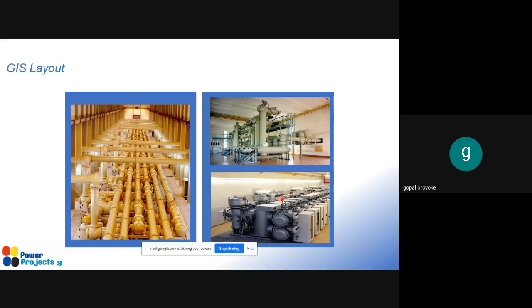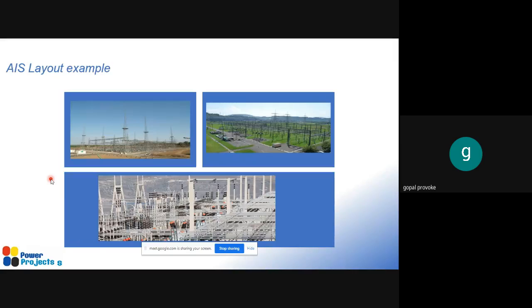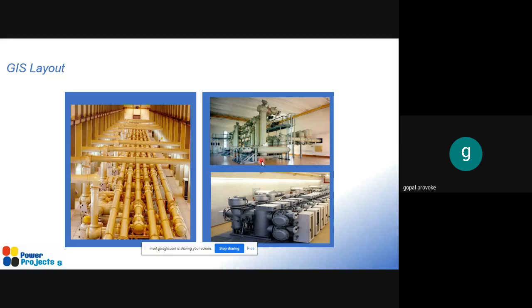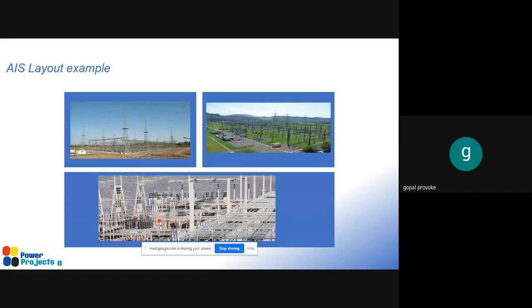And if you have visited metro stations, there is a gas insulated substation near Alandur, and there is a gas insulated substation at Coimbatore metro station also. For areas which have a very high population, where we do not find a larger area for an outdoor kind of substation, mostly in metro cities, they will go for this gas insulated substation. This will occupy very little area, and we can place all the equipment very closely. If you see here, the control panel is here, and all the equipment like breaker and isolator will be very compact when compared to the AIS substation. Since there is only an air insulated medium, we have to place all the equipment apart so that there won't be any flashover or flux interference.